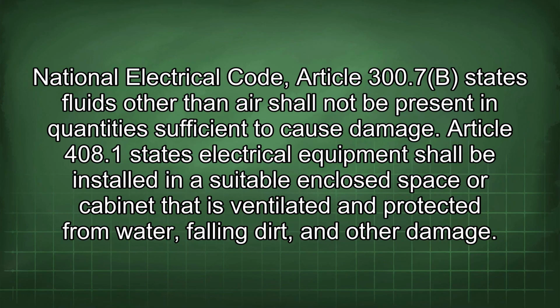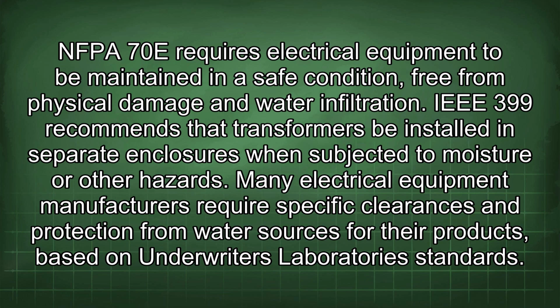National Electrical Code, Article 300.7(B) states fluids other than air shall not be present in quantities sufficient to cause damage. Article 408.1 states electrical equipment shall be installed in a suitable enclosed space or cabinet that is ventilated and protected from water, falling dirt, and other damage. NFPA 70E requires electrical equipment to be maintained in a safe condition free from physical damage and water infiltration.